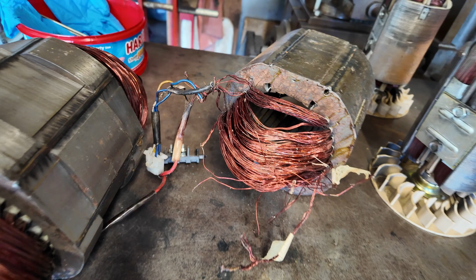These ones are the stator. This one is a single phase one, which I've had to go at pulling apart. You can see where a lot of the wires are burnt, and that actually doesn't look too bad at all. I think it's fairly straightforward, the mains windings. It's just where the exciter coil goes and stuff like that, and the auxiliary 12 volt coil if they've got one.